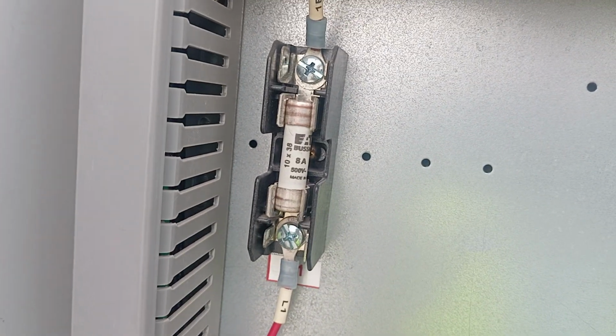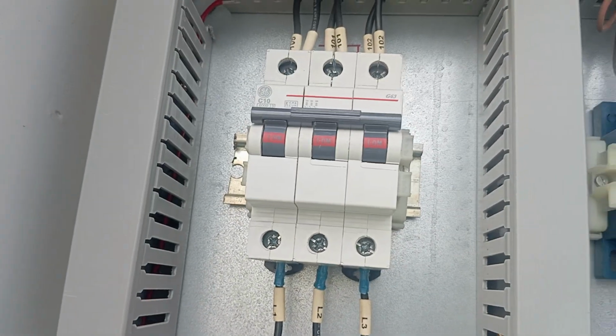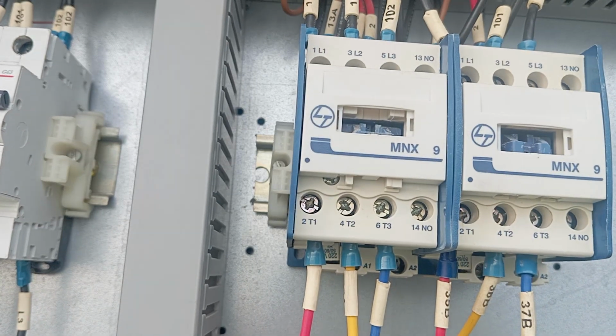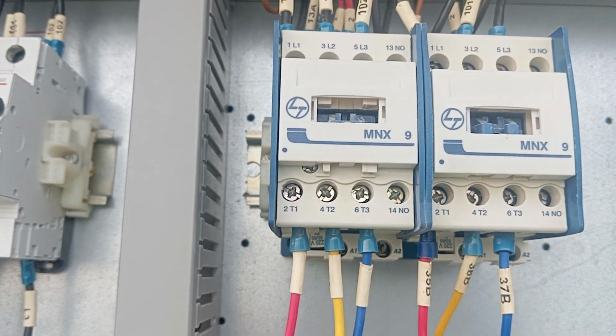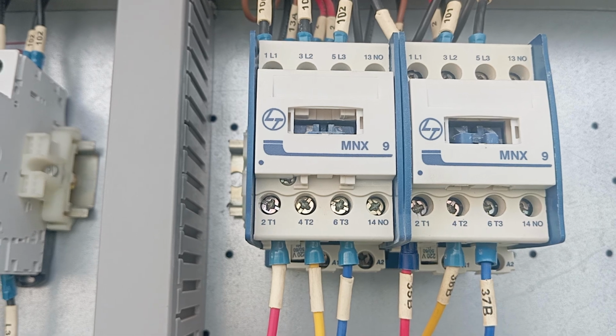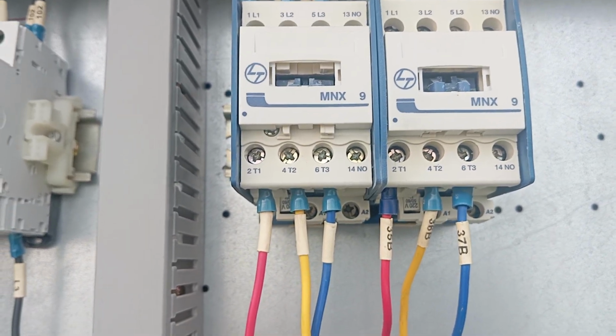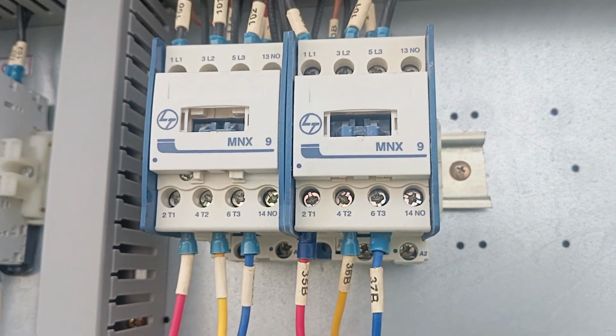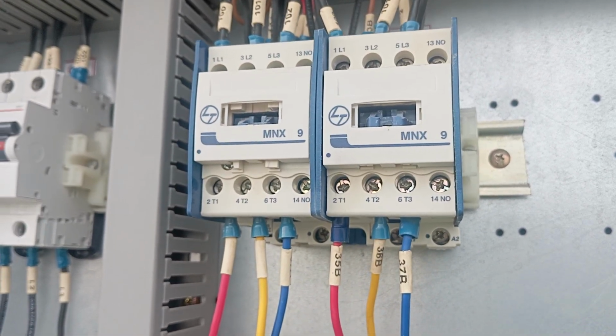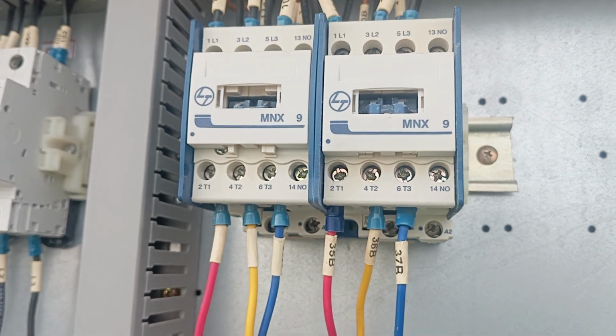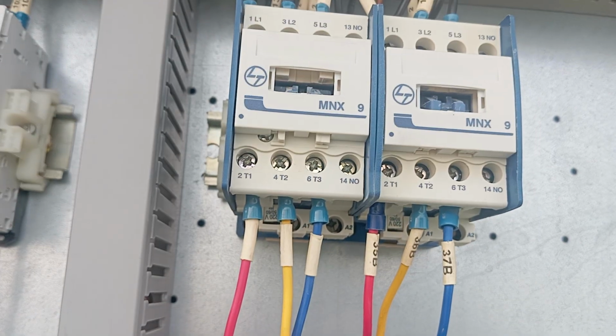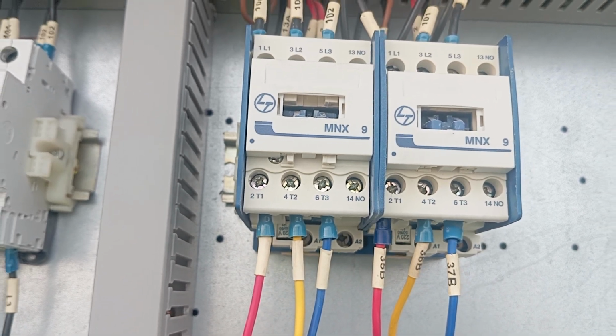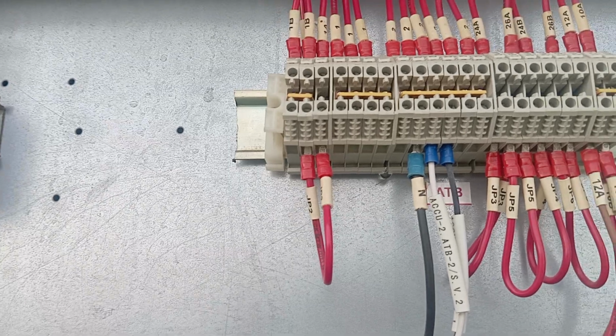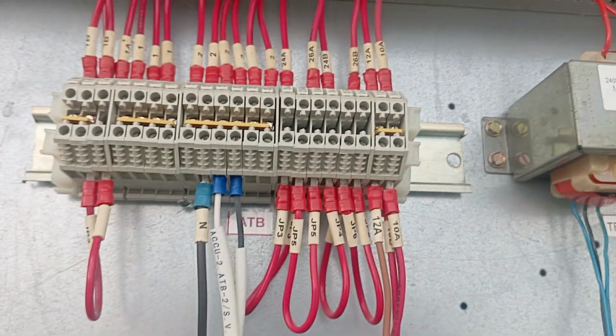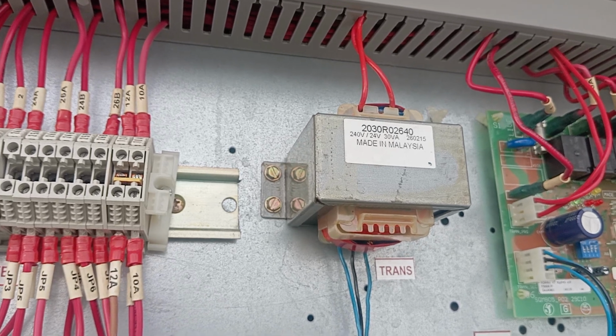Okay, now I am going there. There is a fuse and a circuit breaker, and these two contactors are the condenser coil fan motor contactors. This unit has two condenser coils, two fan motors and two compressors. So it needs two compressor contactor coils and two condenser fan motor contactor coils, and this is the ATB terminal board, and this is a transformer.